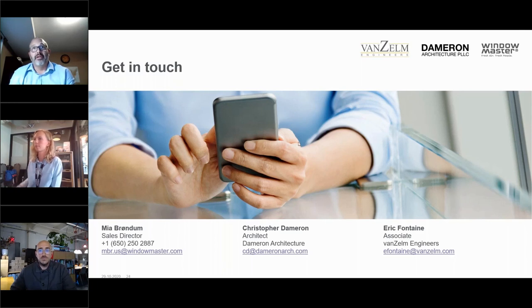The system I used on the Dartmouth project, which Mia is fully aware of, was commissioned and tested right from the beginning, so when it's turned over, you have validation that the system is actually working as intended. That's a big recommendation: make sure you're commissioning, testing, and validating at startup.